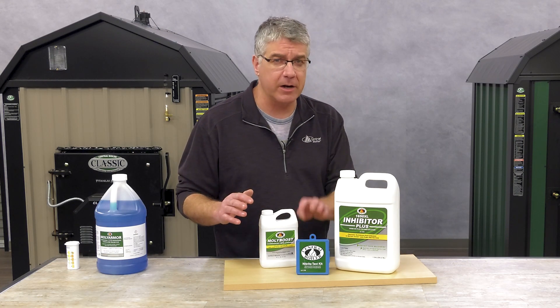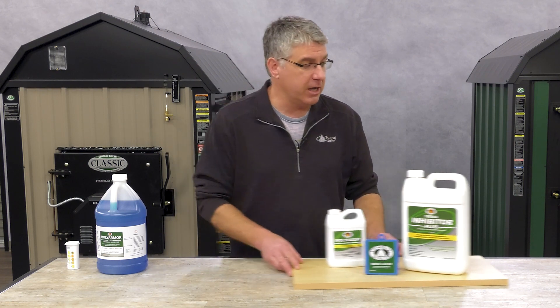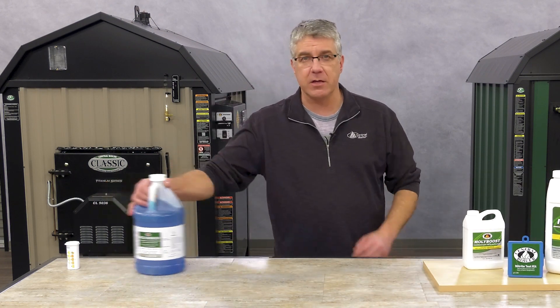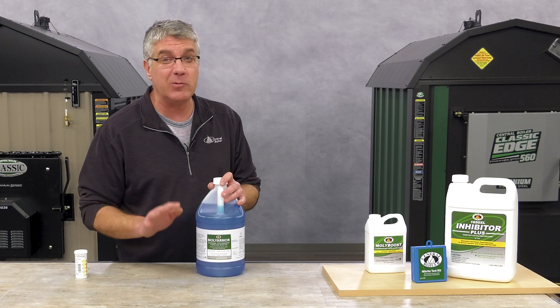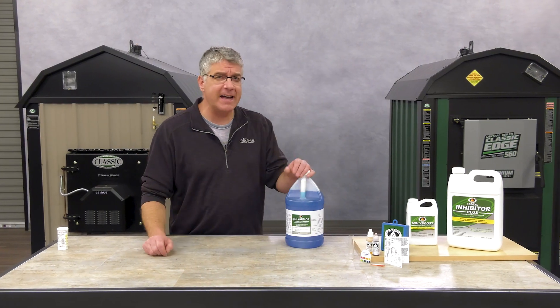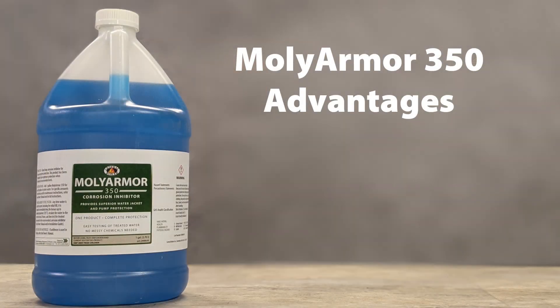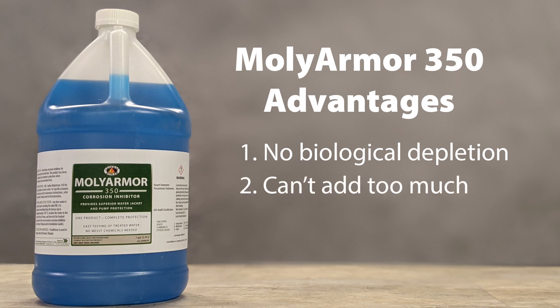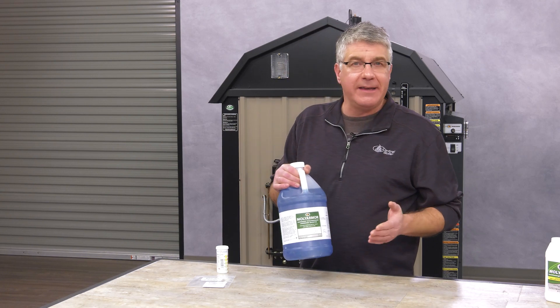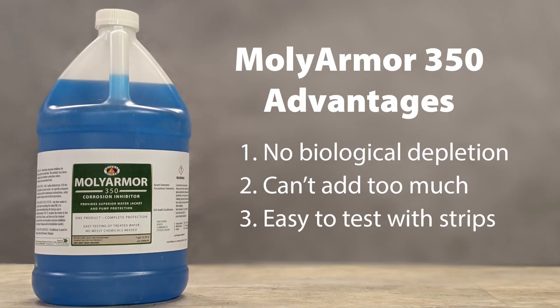However, if you test your water and your parts per million of nitrite are below 1500, then you need to drain your system and add in MolyArmor 350. The reason we switched to MolyArmor 350 had nothing to do with protection — they're both excellent corrosion inhibitors. However, MolyArmor 350 does offer some advantages: it's not subject to biological depletion, you can't add in too much, and it's easier to test.